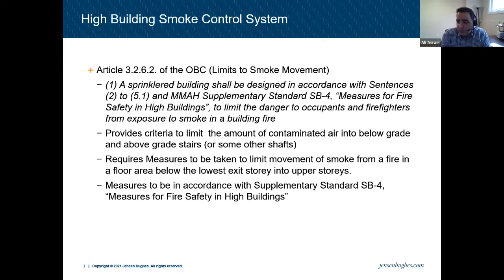And it provides the criteria to limit contaminated air into below-grade and above-grade stairs, for example, or some other shafts, depending on the measures that we're using. We're going to be talking about it later. And it requires some measures to be taken, and all those measures come from Supplementary Standard SB-4. The name of that is Measures for Fire Safety in High Buildings.